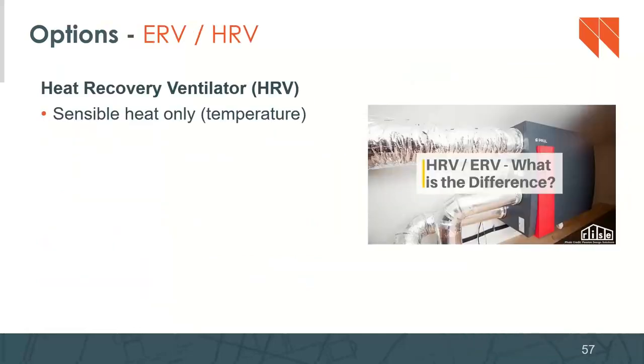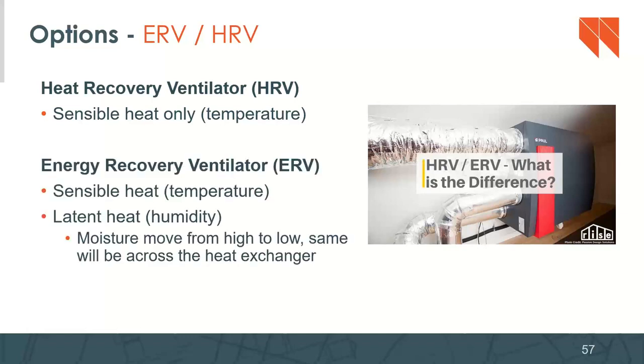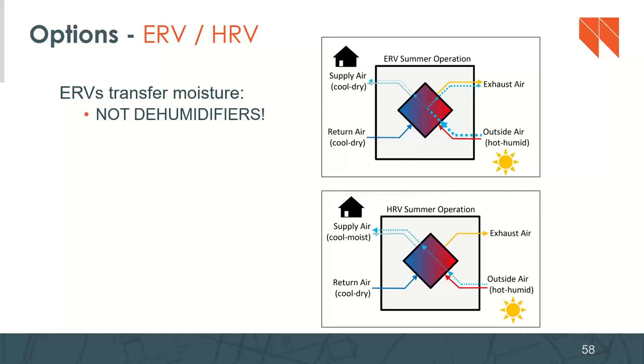All right, ERV, HRV. So a heat recovery ventilator, an HRV, is going to transfer sensible heat only. So it's just the temperature, the heat that you can sense. An energy recovery ventilator, an ERV, is going to transfer sensible heat, but it's also going to transfer latent heat in the form of humidity. So moisture is always going to move from high to low. Just like we said about heat moving from warmer to colder, moisture is going to go from a high concentration to a low concentration. And the same is going to happen across that ERV core. So ERVs transfer moisture, but they are not dehumidifiers.